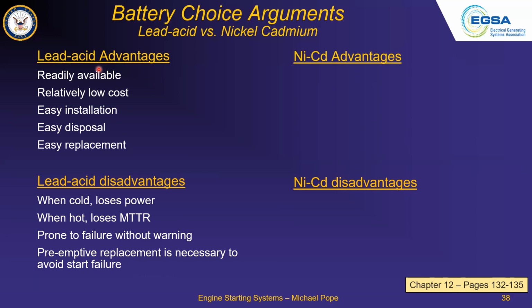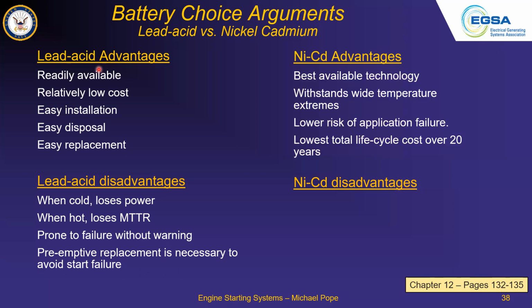What about temperature? What effect does temperature have on the NiCads? Probably the opposite of lead acid, so probably less impact. Yeah, you're right, it's less affected by temperature extremes. So it is the best available technology for temperature extremes, low risk of application failure, and it can have a lower total life cycle cost over 20 years.